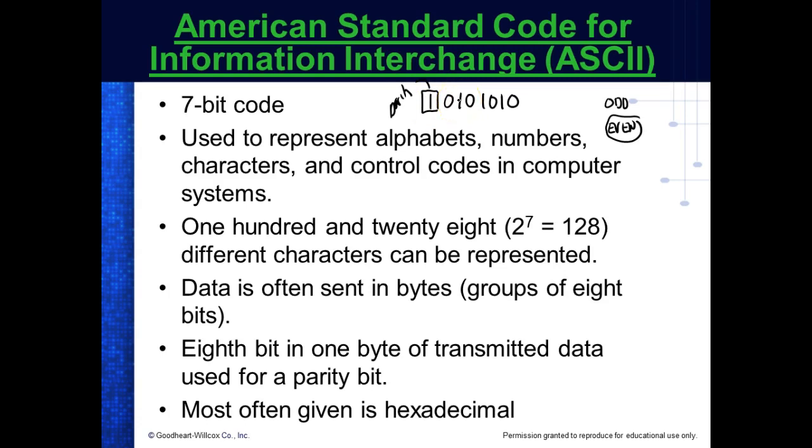The receiver would come up here and count the number of ones. If it came up with an even number, it says it's okay. If it came up with an odd number, it would say it's not okay. Right? Does that make sense? Now, your transmitter and your receiver both had to be set up exactly the same. And y'all see this: some of our PLCs use the old RS-232 port, and you'll see it's got parity up there.